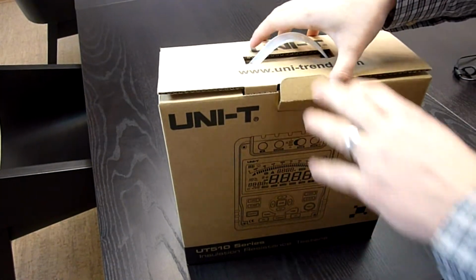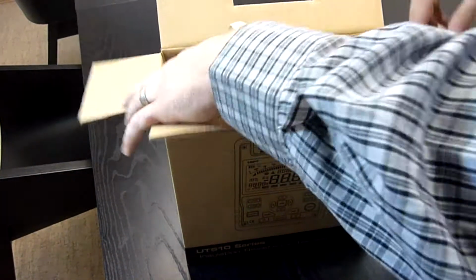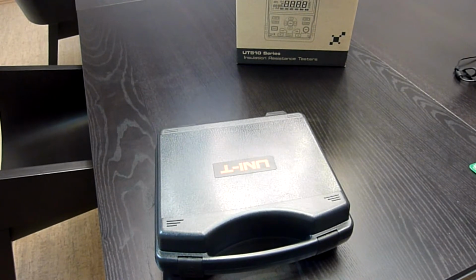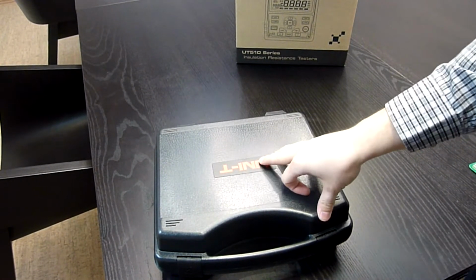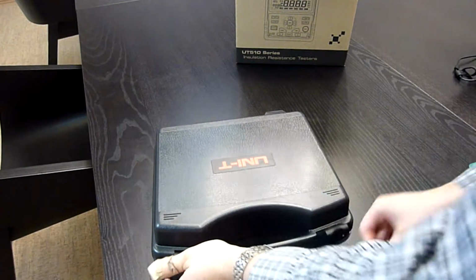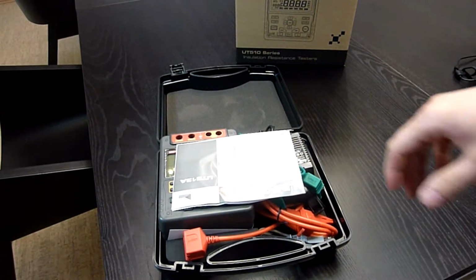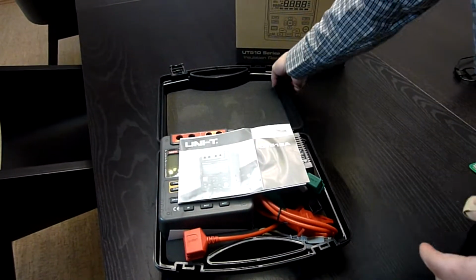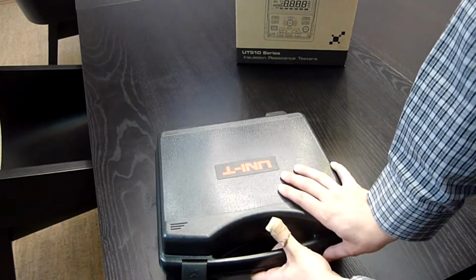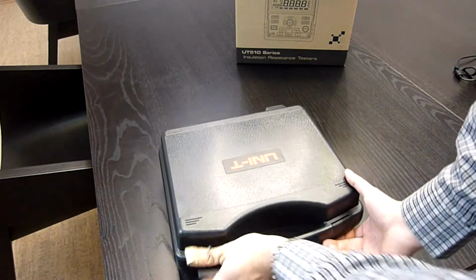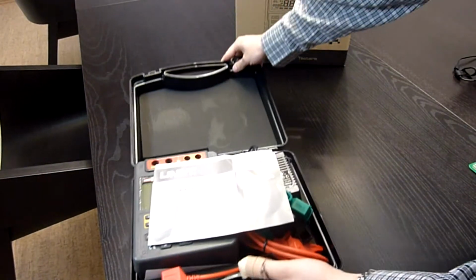We have UT513A here, which is the improved old 513. The main improvements are that the new meter 513A is not freezing during the permanent short. It continues the measurement, and it also measures the actual value on the display, so you know precisely what the testing voltage is. As you can see, the meter is in a plastic box, which is kind of tough, very easy to wash. You can put it into the trunk with other tools. It will be enough protection for your meter.